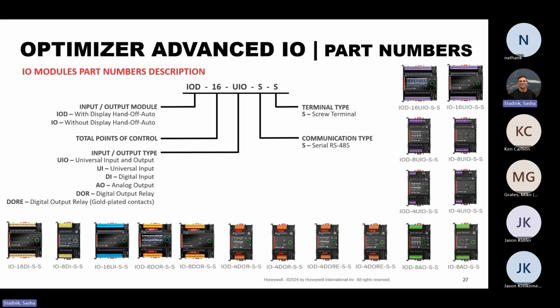That's great because when you change I/O modules, or want to send them from your office to the site, you can configure them in your office and send them to the site easily. Or if you don't want to send someone to the site, the person there can do it via the display. You just tell them, input number one is going to be binary input, on/off, 24 volt, and so on. You don't need someone to go to the site to program the I/O module.